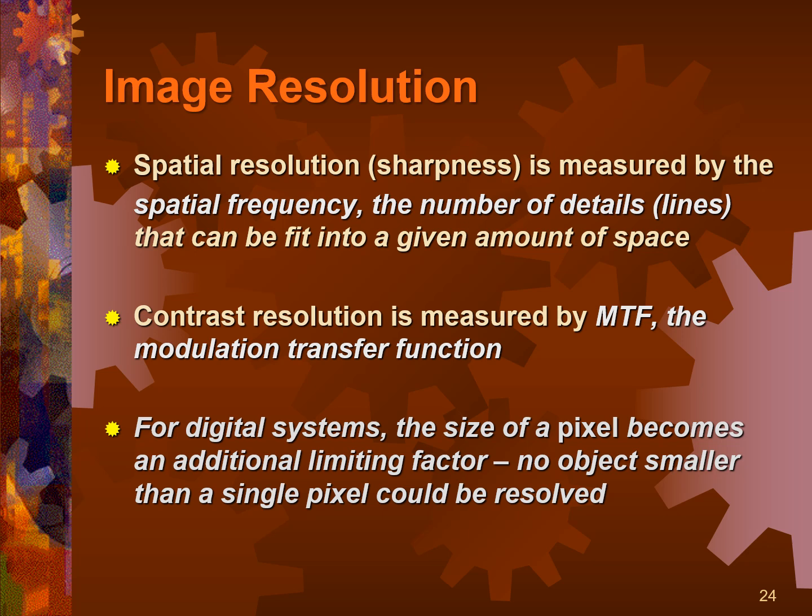What I'm suggesting to you is we can create a phantom that has lead strips with interspace like a grid, okay? But we can put those lead strips so close together and make the thickness of the lead strips smaller than the width of a pixel. And then make the inner space also smaller than the width of a pixel, and you won't be able to radiograph the difference, even though you can visually see that's definitely lead, plastic, lead, plastic, lead, plastic.